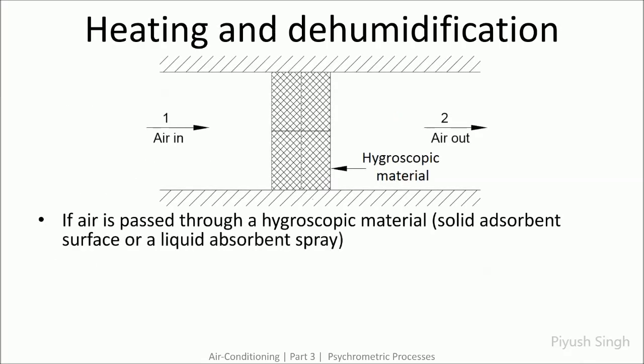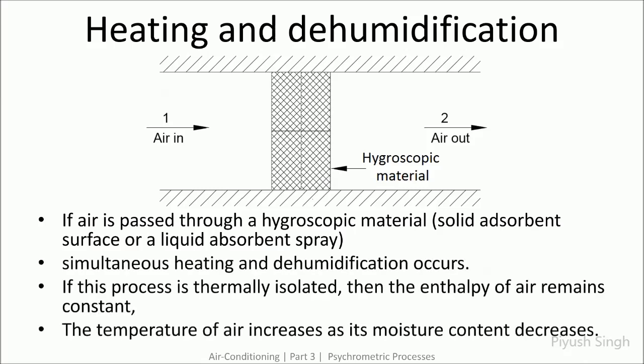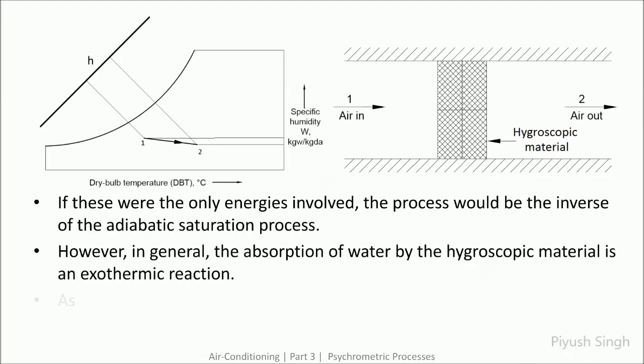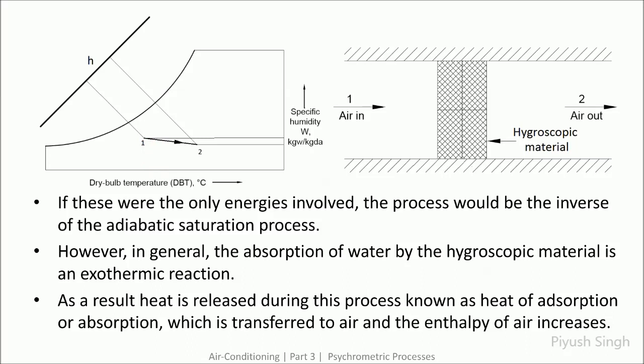The next process is heating and dehumidification. In this case, the air is passed through a hygroscopic material, which may be a solid absorbent or a liquid absorbent spray. Due to this process, simultaneous heating and dehumidification occurs. If the system is thermally insulated, the enthalpy of air remains constant; temperature of air increases as its moisture content decreases. Although the absorption of water by hygroscopic material is an exothermic reaction causing an increase in enthalpy, for all numerical calculations this process is assumed to be a constant enthalpy process unless otherwise mentioned.